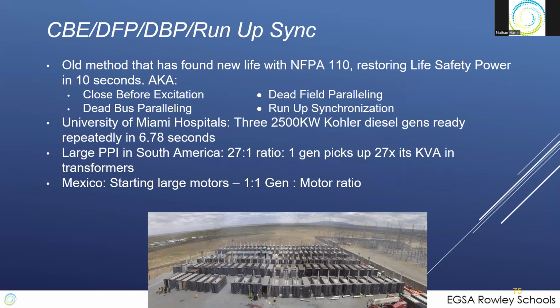It's called close before excitation, dead bus paralleling, dead field, run-up sync. They are all the same thing, just different people use different terms. We did it at University of Miami hospitals. We got three 2.5 meg Kohlers up and online repeatedly in 6.7 seconds. That's pretty amazing, three big machines online in 6.7 seconds.